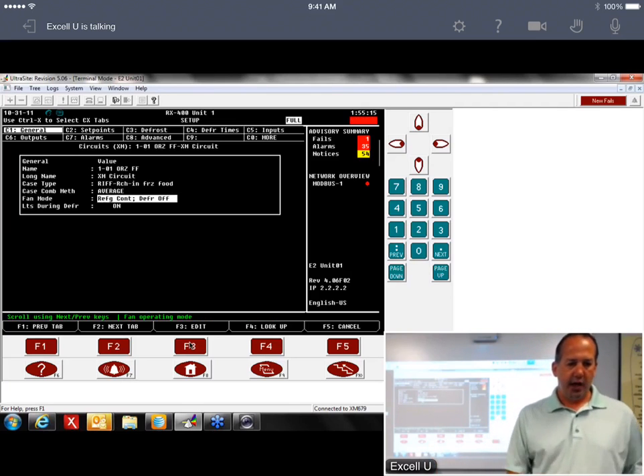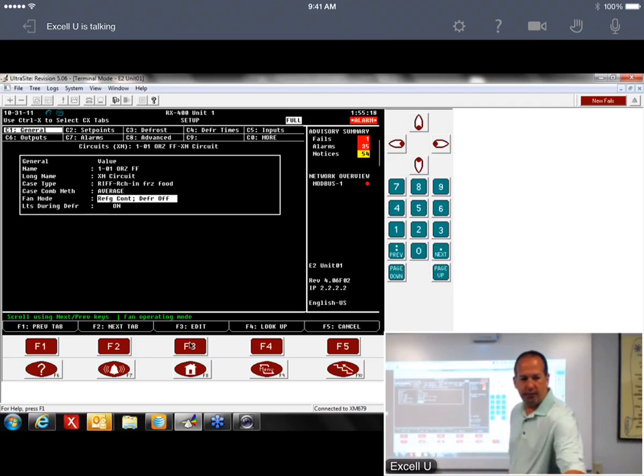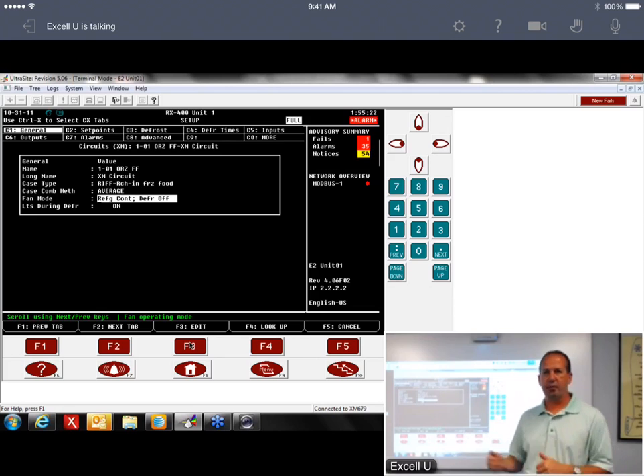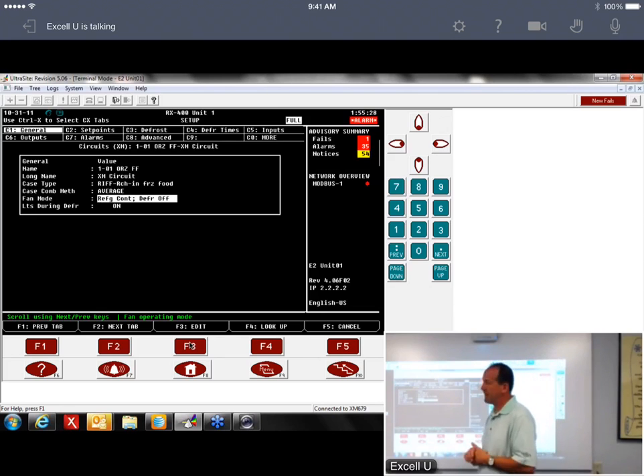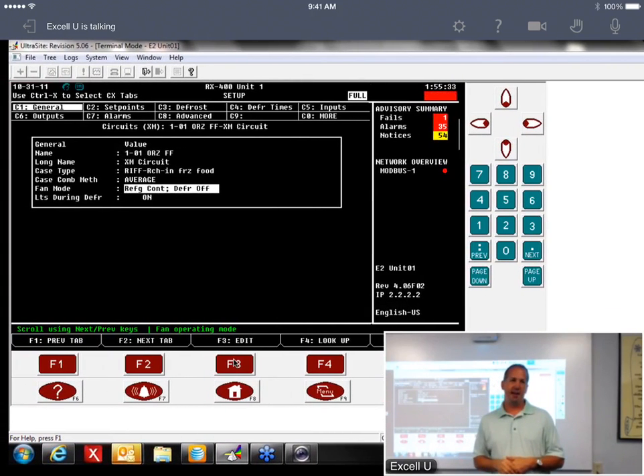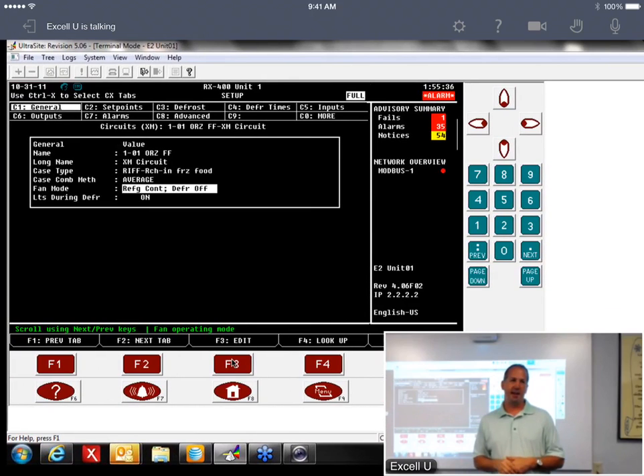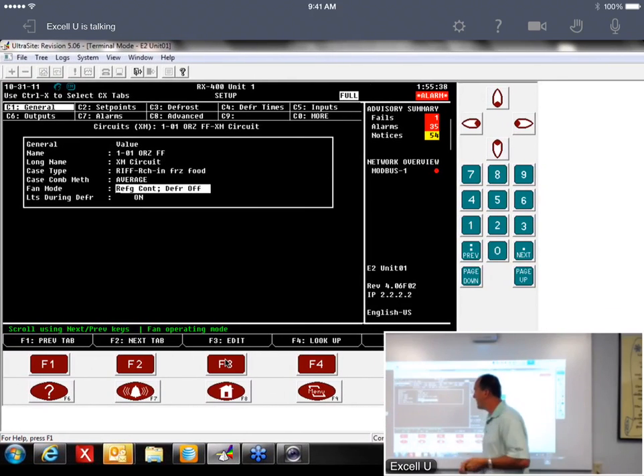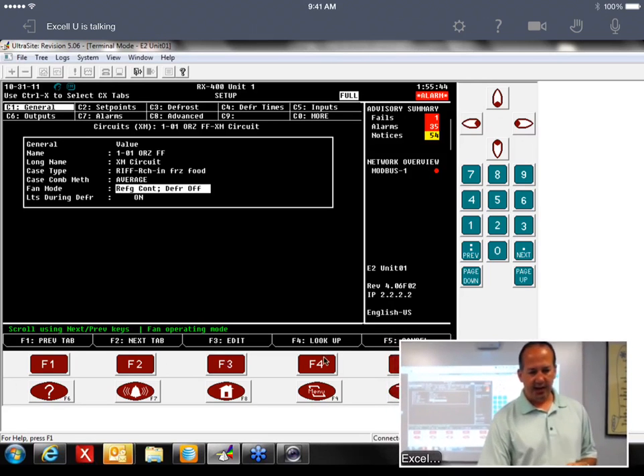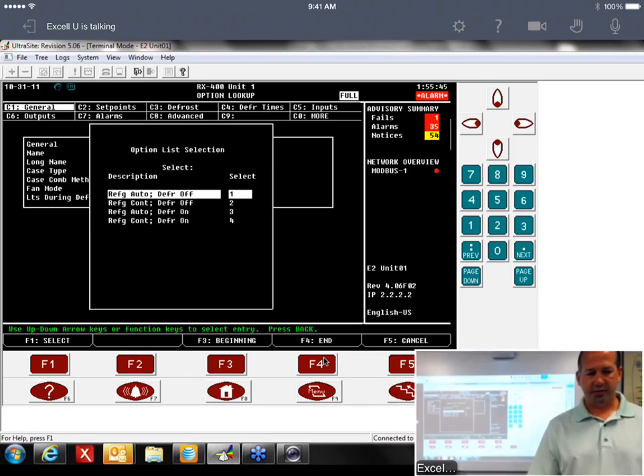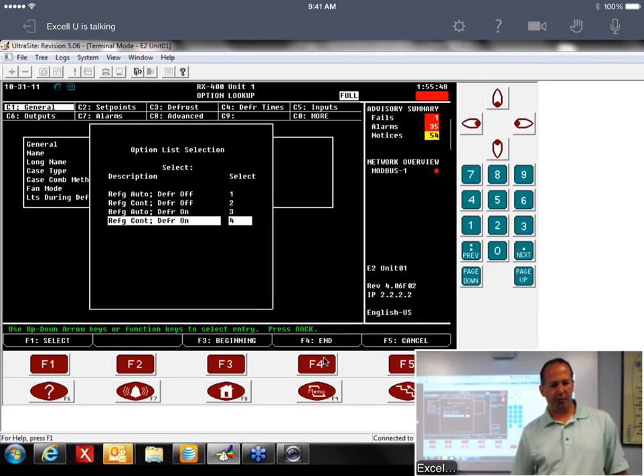The next thing too, fan mode. The fan mode tells you what your fans are supposed to do during defrost and refrigeration. It does not get changed with case type. So if I select an ice cream case, it's not going to change that fan type, so you still have to change the fan type. For electric defrost, we want them on in refrigeration and off in defrost. Off cycle, we would change that to on during defrost. So it would be option 4, refrigeration continuous defrost on.